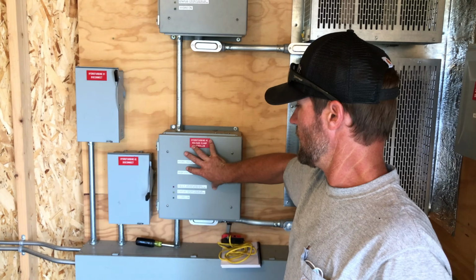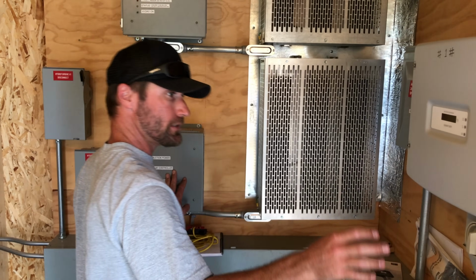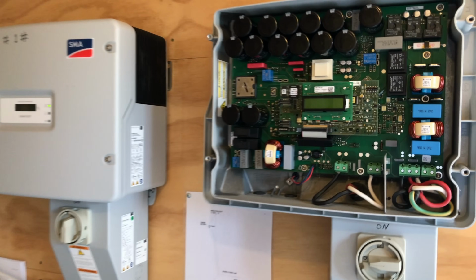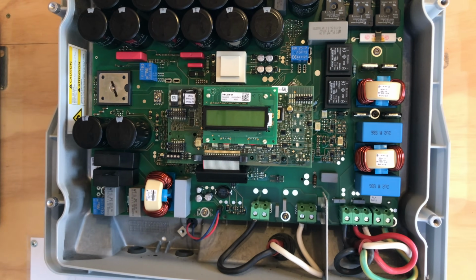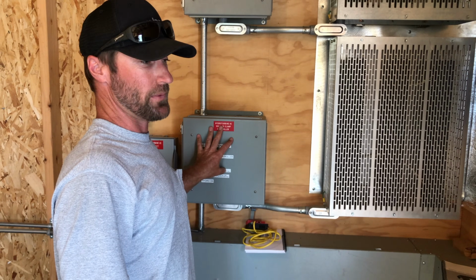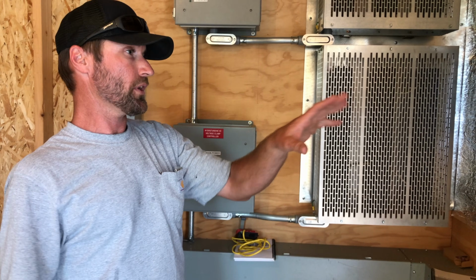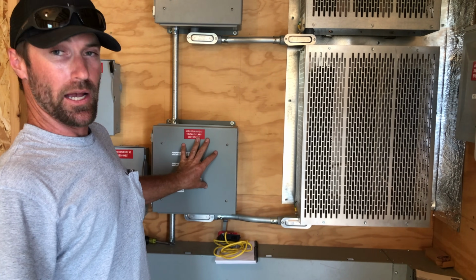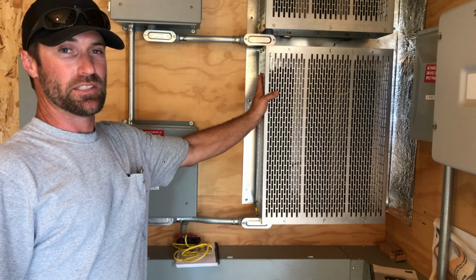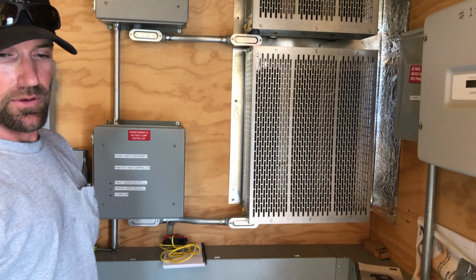and rectifier, which converts the AC signal to a DC signal, and that's what feeds the inverter on a DC input. It's a standard solar inverter, and everything is the same as a grid tie solar system from here on out to the grid. The controller not only converts the signal from the wild AC to the DC signal for the inverter, but it also acts as a shunt diversion. So if the grid goes down, it will take the power from the hydro generator and will shunt it in this resistive load as heat, and that's just a safety precaution in case the grid goes down or there's some other issue. And that's the gist of how the system works.